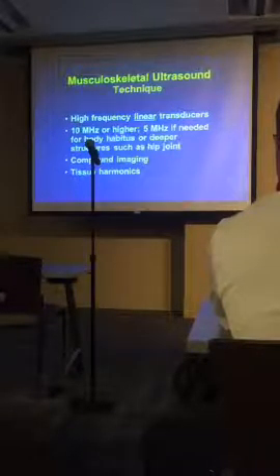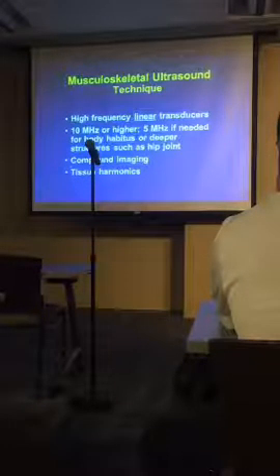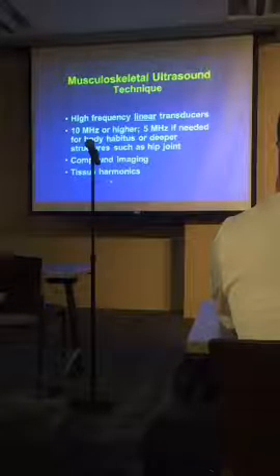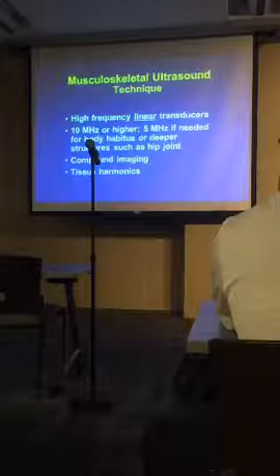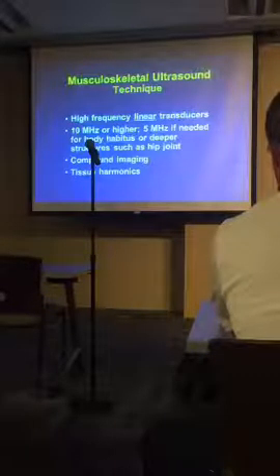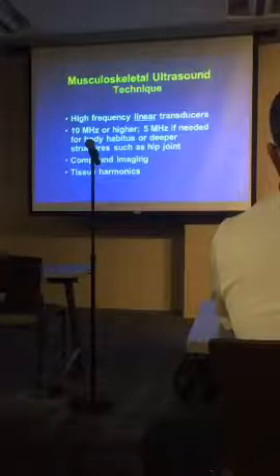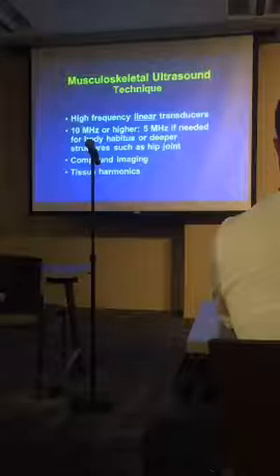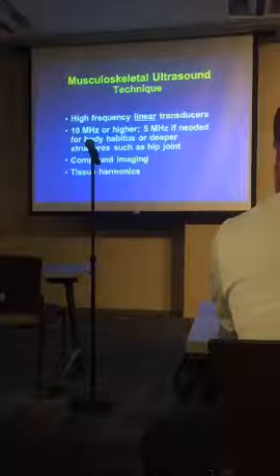Tissue harmonics is another tool present on many ultrasound machines, though it is not as important in musculoskeletal imaging. Rather than listening for the frequency sent out, it listens to multiples of that frequency, theoretically giving a sharper image. But since we're already imaging at such high frequency in MSK, I don't find tissue harmonics to be particularly helpful.